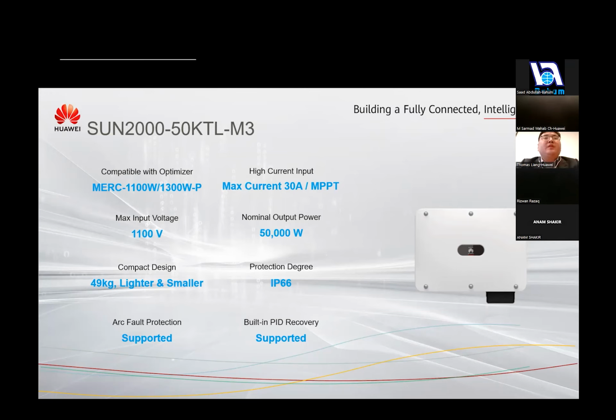And it will support IP66 to make sure the inverter can keep the best performance in every harsh scenario. It will also support the arc fault protection function, and it will detect fire risk on the DC side, and the inverter will shut down within 0.5 seconds to make sure there's no fire risk in the whole system. And it will support the PID recovery function.